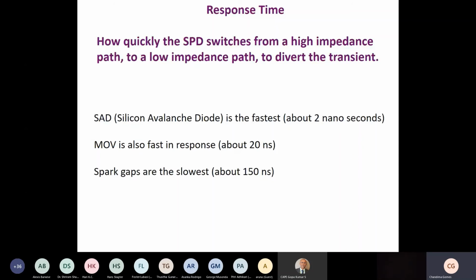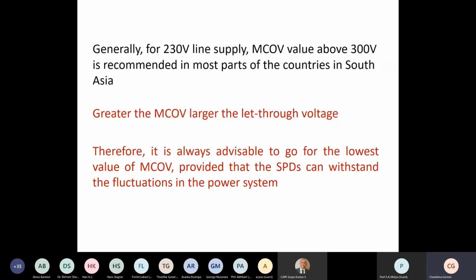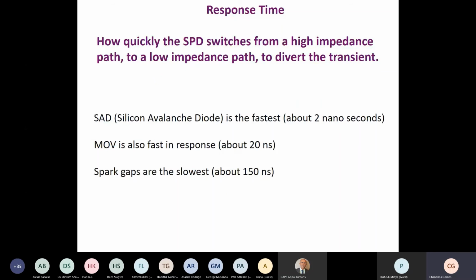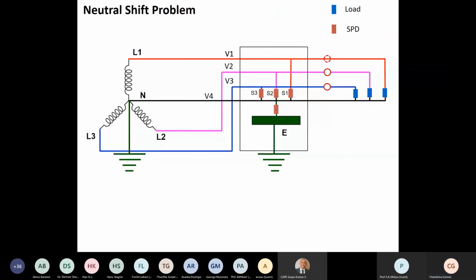Because when the MCOV increases, naturally the UP value of the SPD will also increase. Therefore, you can't go for very high values of MCOV if you want lower values of UP. And then response time, I'm just skipping because response time is not that important nowadays. If you select your UP, then response time does not mean much.